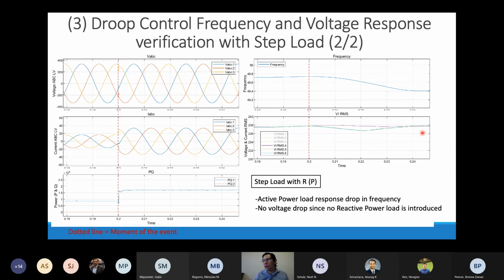In the following figure, I'm showing the same case study, but in this case we are introducing a step type of load which is entirely resistive. As the droop control literature mentions, we have a drop in the frequency, correct? But since our load is entirely resistive, we have a transient when the load kicks in and it settles down at basically the same voltage as before. So our voltage is not reducing as we expect. And this event happens in a cycle.